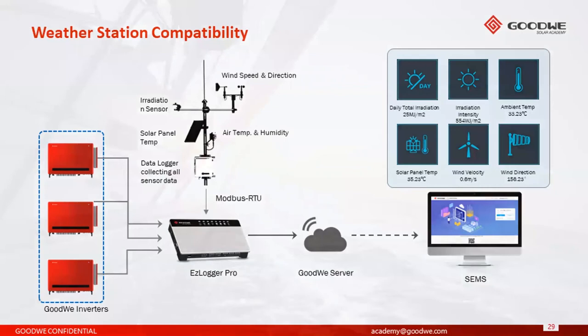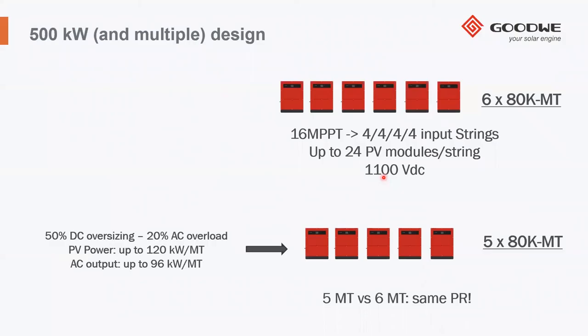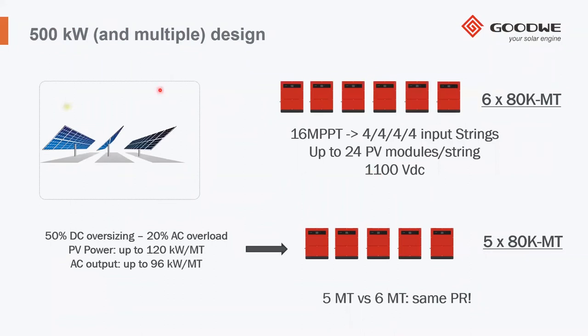Coming now to the specifics of the Greek market. For the Greek market, for a typical 500 kilowatt project, or also for multiples of 500 kilowatt, what is our recommendation? Our recommendation is the use of six machines of the 80K MT that you can see here. With these six machines, you have 16 MPPT available with a 4444 input string, up to 24 PV modules per string and 1100 volt DC. This is already proven on the Greek market, works very well. It allows you to use only six machines, so it's a saving also in terms of cost. It's reliable, proven, and it works perfectly.